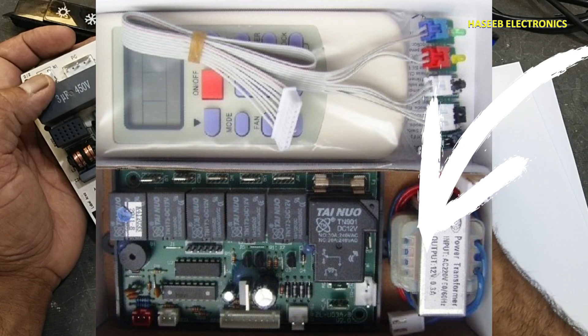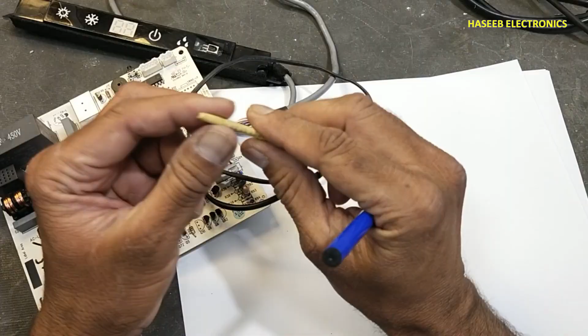Because it is using a microprocessor, to power up the microcontroller it has a power supply section, that is a low voltage power supply. In the split unit there was a transformer, but here it is using electronic control. To sense the room temperature, it is using an NTC here. It is a negative temperature coefficient resistance. And to check the cooling, whether the compressor is working or not, it has this tube temperature sensor. It will sense the ambient temperature, the air temperature in the room, and it will sense the cooling. Here is the display, and here is the swing motor, the louver motor. It will move the flappers to direct the air in any direction.